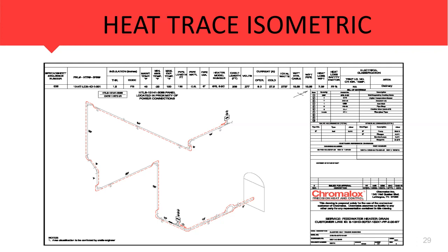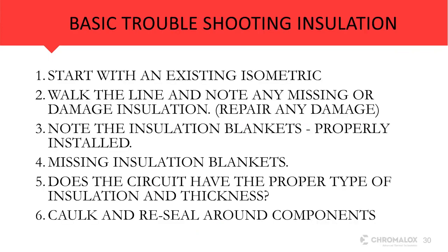If we're looking at insulation, the best thing to do is to take that isometric and walk the line and note any damaged insulation, any missing insulation we may have. Do we have any insulation blankets? Are they properly installed? Do we have insulation blankets that are missing? Many a time I've been to a site to look at a trouble area and the insulation blankets are sitting there laying on the ground. That's not going to help us. So make sure those things are on, they're tight, they're properly installed.